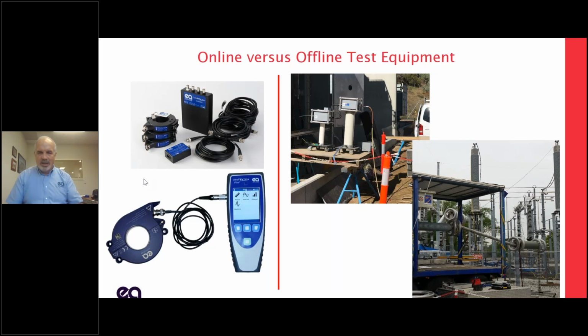The picture on the lower right is a 60 hertz or a line frequency test where they're actually energizing it at 60 hertz, which is better than 0.1 hertz. It's going to have more of a realistic effect. But this was 3 tractor trailer loads of equipment just to energize these cables to 300 kV. So your test equipment gets very large for offline testing. So I've got to take an outage. I've got to have very heavy test equipment and a lot of money and time involved.